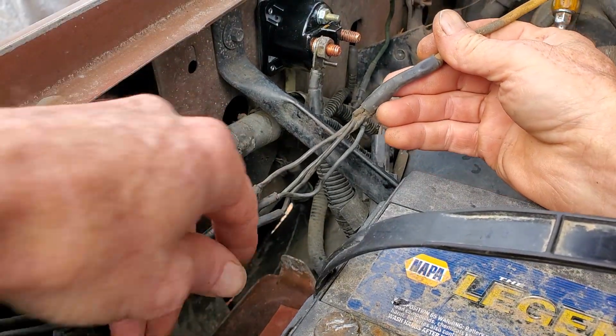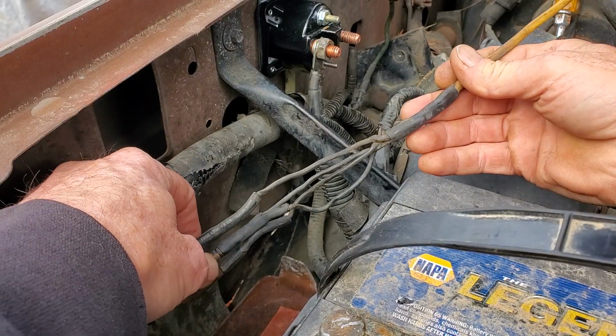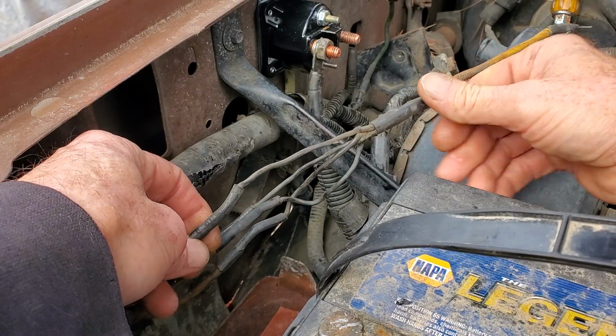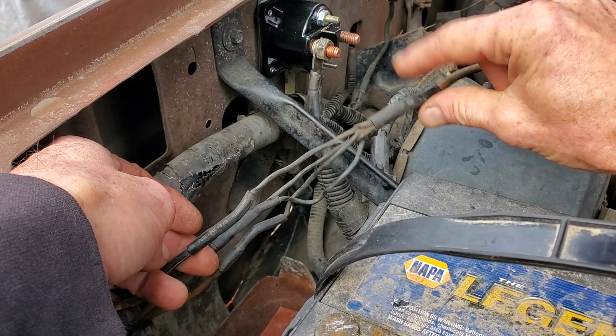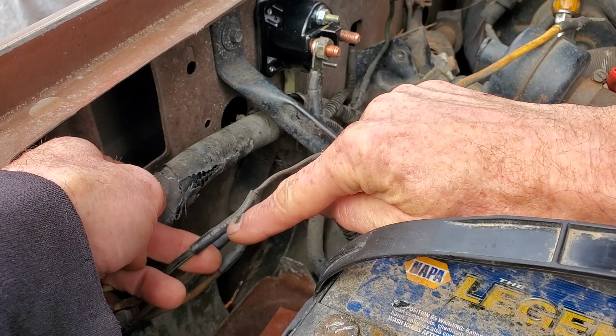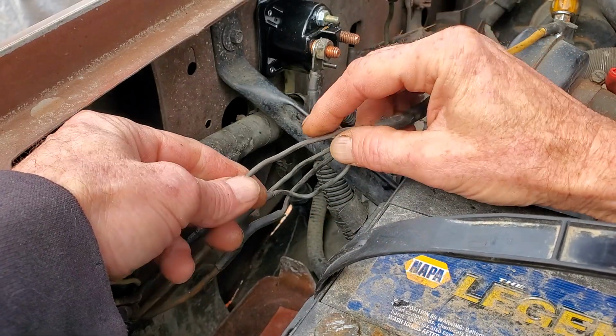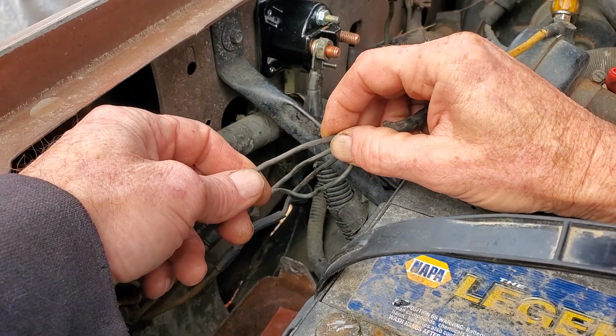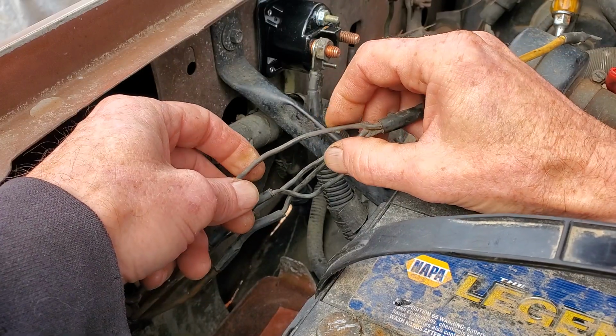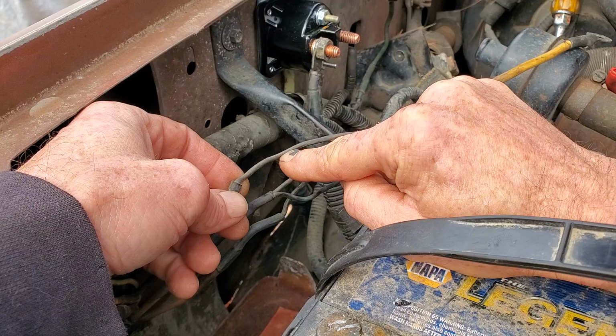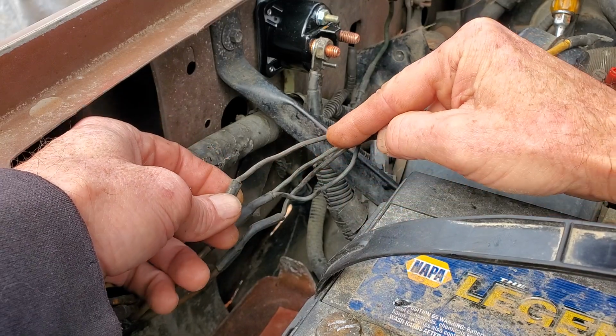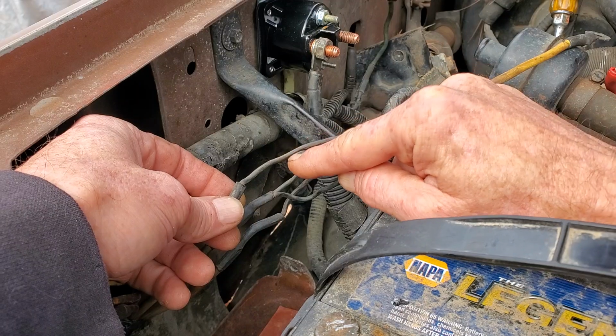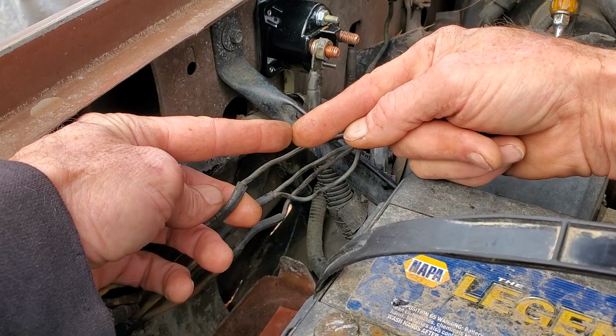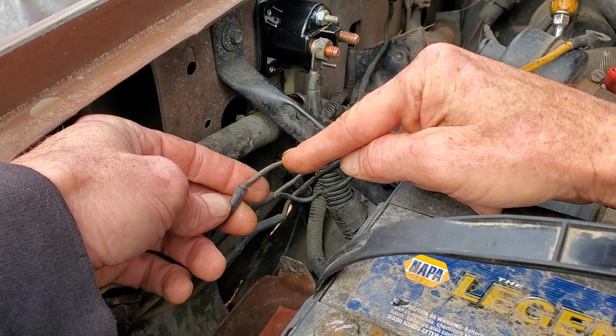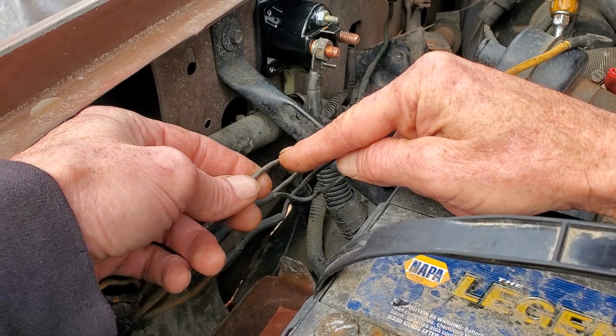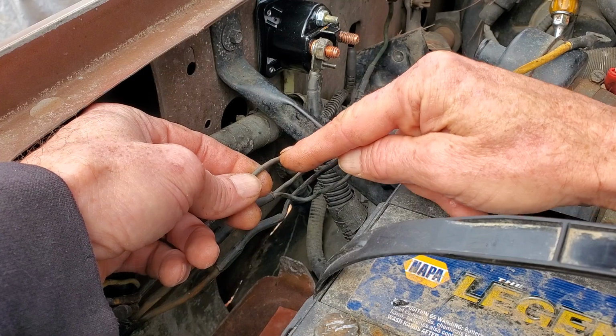What they do is they act like a fuse. They protect the wiring to prevent fires, but fuse links, from this point here, this is a splice with heat shrink. This is a splice with heat shrink. But this material right here, the insulation is made of a material that if the interior conductor melts open because you've drawn too much current due to a fault, the wire inside the insulation burns open, but the insulation will maintain its integrity and not melt, and it will help prevent fires.